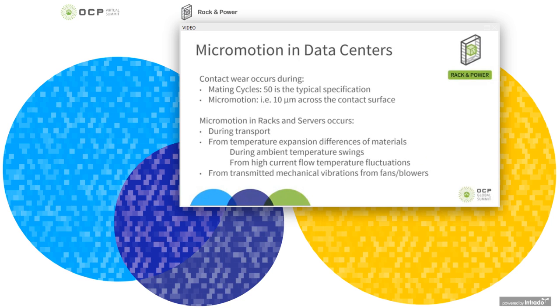So where can this micromotion occur? You can see contact wear for mating cycles, right? You kind of expect that. But micromotion occurs with a very little bit of movement across the contact surface, and that can occur during transport. It can occur during temperature expansion and contraction if the materials are expanding at different coefficients of expansion. And it can also see transmitted mechanical vibration from fans and blowers.